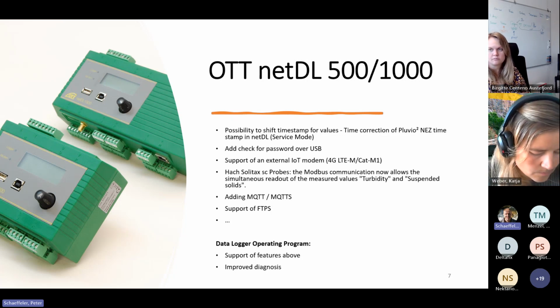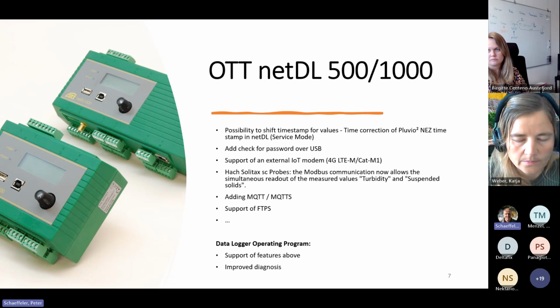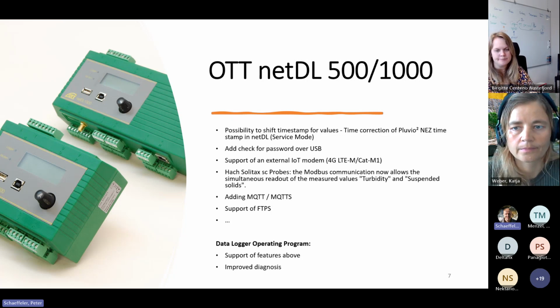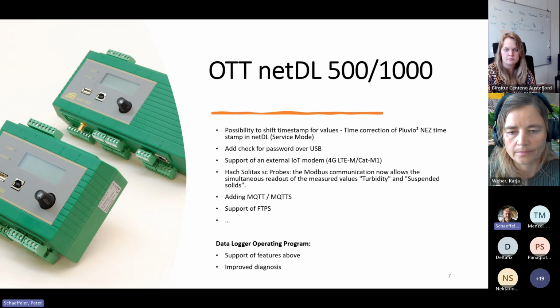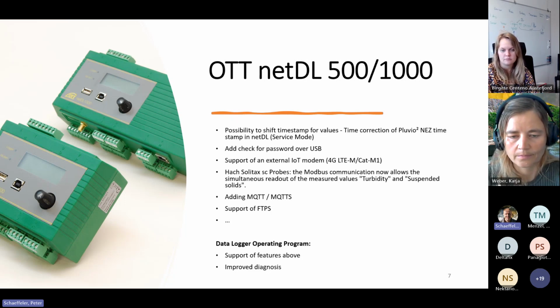One niche feature: we can connect the HACH Solitax probe via Modbus to the NetDL. With a HACH Solitax, you can measure turbidity or suspended solids using the HACH controller, but you have to change the settings in the SC200. With NetDL, you can measure both, one after the other, in the same measurement cycle, which is a quite unique feature for the HACH Solitax probe.